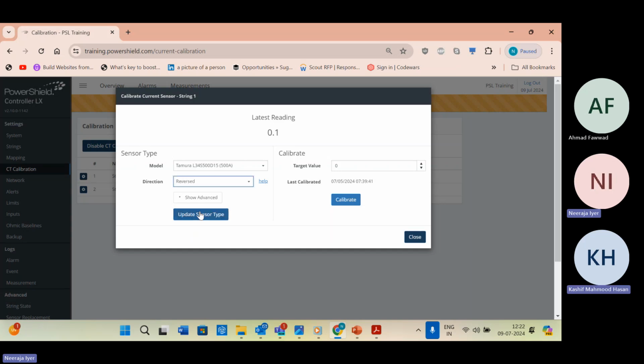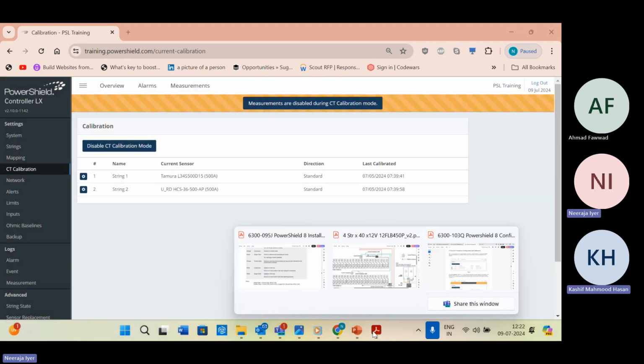In our case, we have 40 batteries in series, and our team fixed this CT on the positive cable of battery number 1. Okay, and this cable is going to the breaker to the UPS also. You should check that arrow direction. The arrow direction is the same, meaning from battery number 1 to battery number 2.